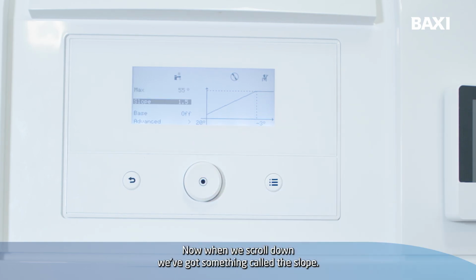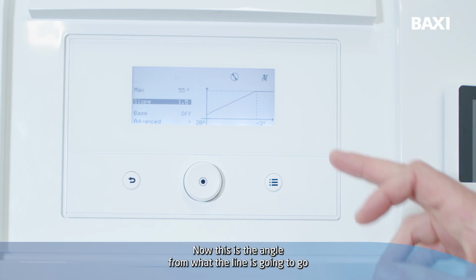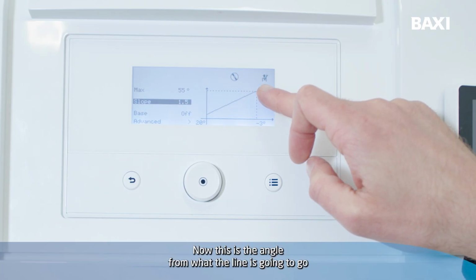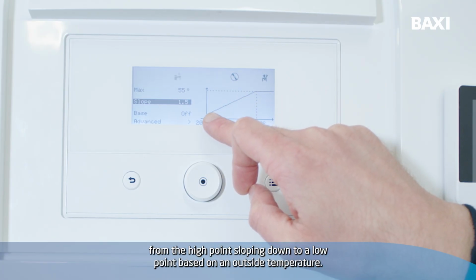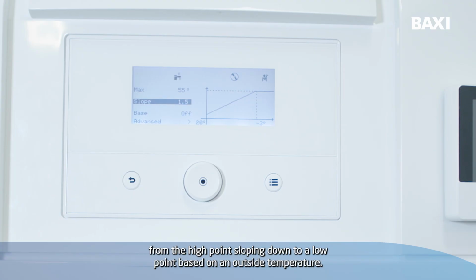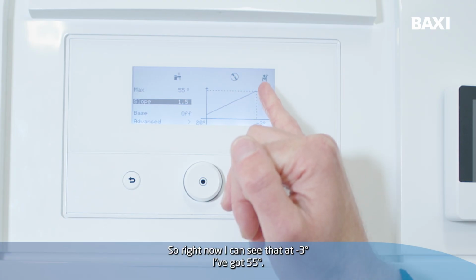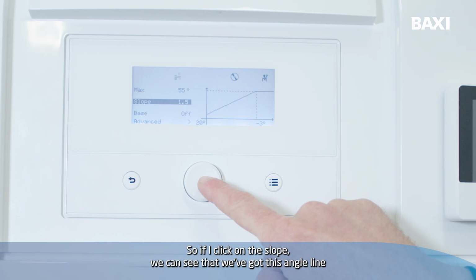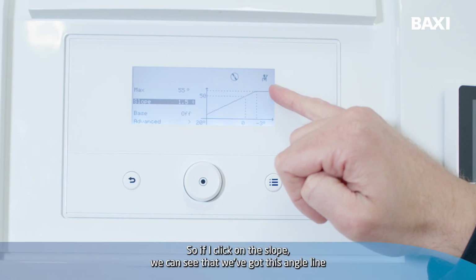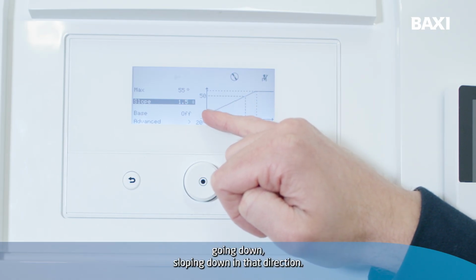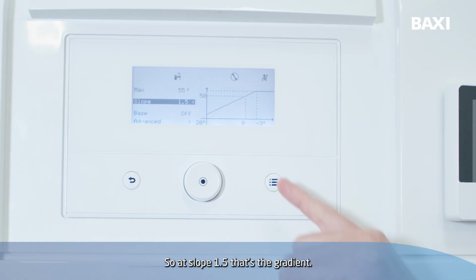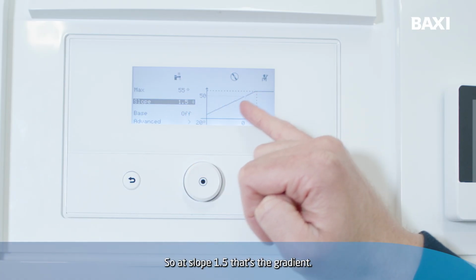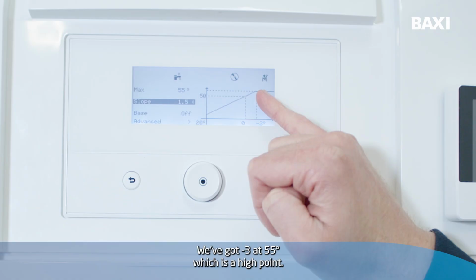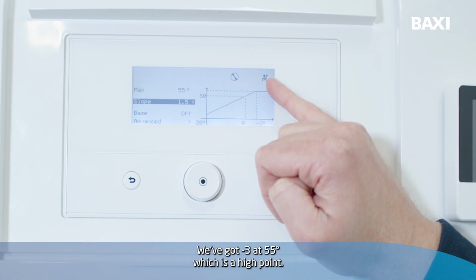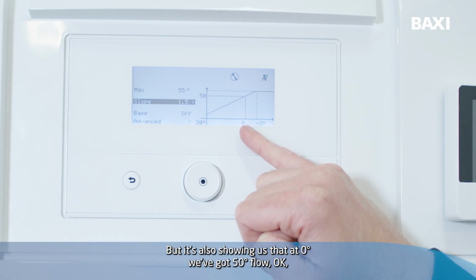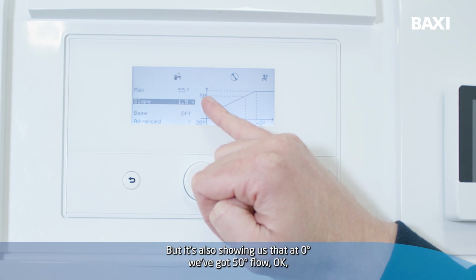Now when we scroll down, we've got something called the slope. Now this is the angle from what the line is going to go from the high point sloping down to a low point based on an outside temperature. So right now I can see that at -3, I've got 55. So if I click on the slope, we can see that we've got this angle line going down, sloping down in that direction. So at slope 1.5, that's the gradient. We've got -3 at 55, which is a high point, but it's also showing us that at 0 degrees, we've got 50 degrees flow, okay?